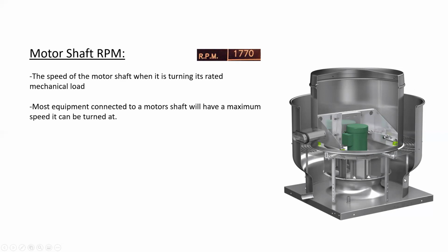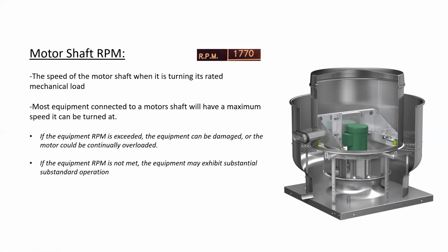Now, if we put a motor on here that turns too fast or turns too slow, we will have problems. If the equipment RPM is exceeded, so I put a motor on that turns too fast, the equipment could be damaged, or the motor could be continually overloaded, because as I continue to increase the speed of the fan, the wind resistance will also increase. If the equipment RPM is not met, the equipment may exhibit substantial substandard operation, as in the suction capacity of the system might be ridiculously low and therefore not be of use within the restaurant environment.